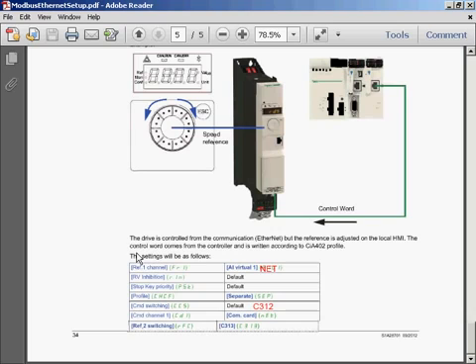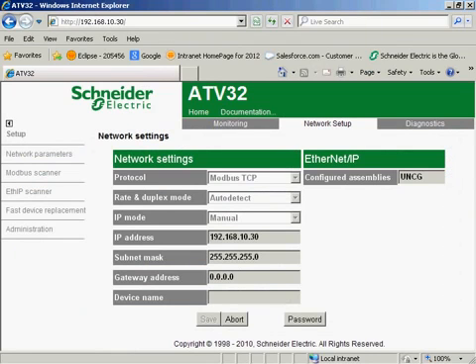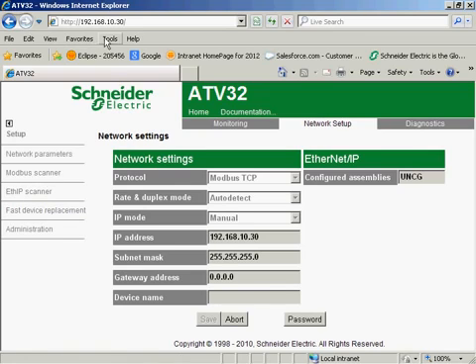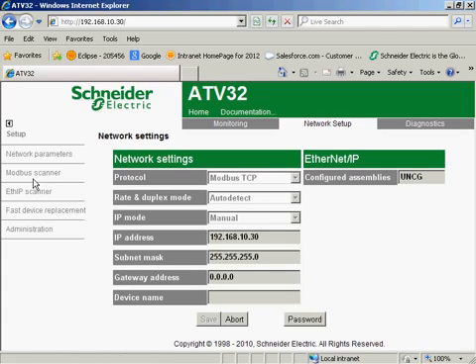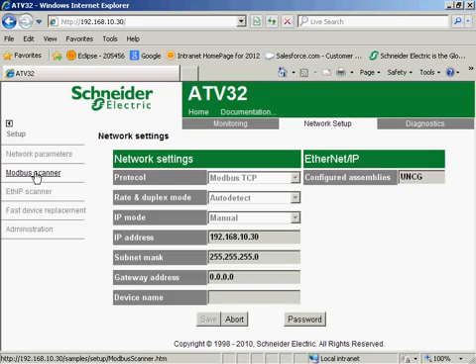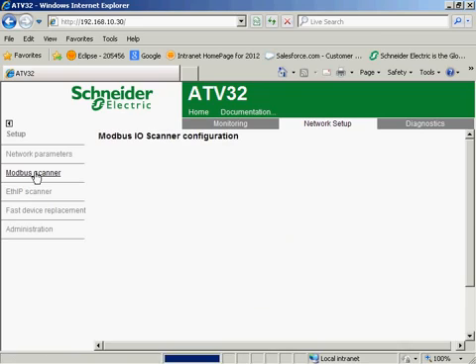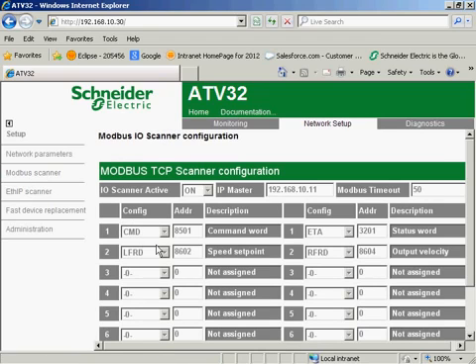So as we move forward, you can also program the drive via the webpage. So I've got two webpages. Here's the IP address of the drive. I showed that to you earlier. I've got the network settings set up at Modbus TCP. The IP address, the subnet. I've got no gateway. And if I scroll through to the Modbus scanner, you'll note that I have the I.O. scanner on. And these are my command word, speed set point, status word, and output velocity, just like we did from the keypad of the drive.